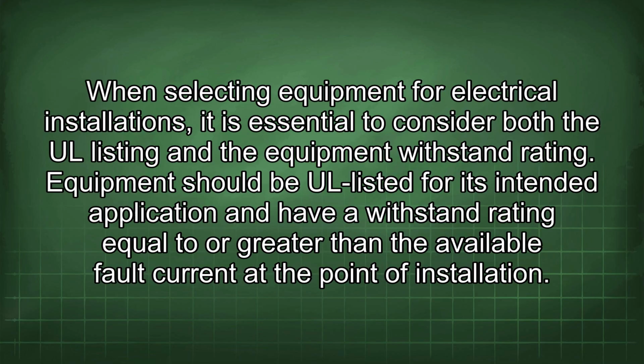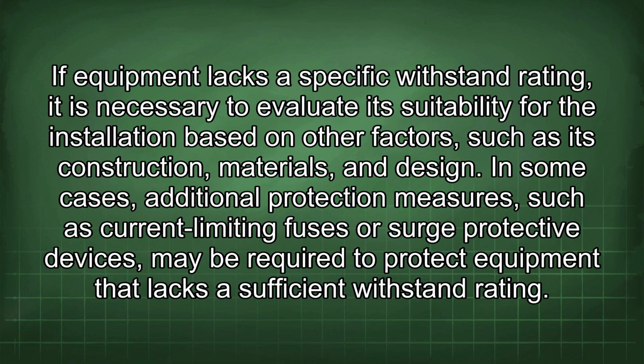When selecting equipment for electrical installations, it is essential to consider both the UL listing and the equipment withstand rating. Equipment should be UL listed for its intended application and have a withstand rating equal to or greater than the available fault current at the point of installation. If equipment lacks a specific withstand rating, it is necessary to evaluate its suitability for the installation based on other factors such as its construction, materials, and design. In some cases, additional protection measures, such as current limiting fuses or surge protective devices, may be required to protect equipment that lacks a sufficient withstand rating.